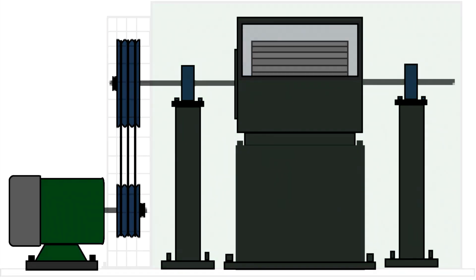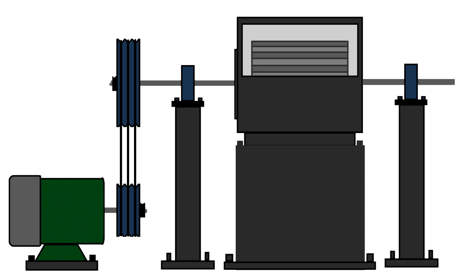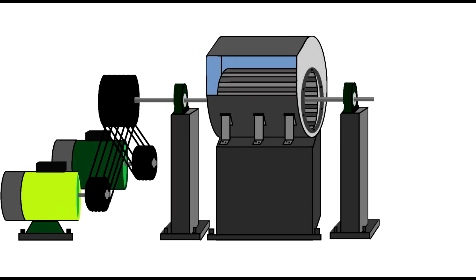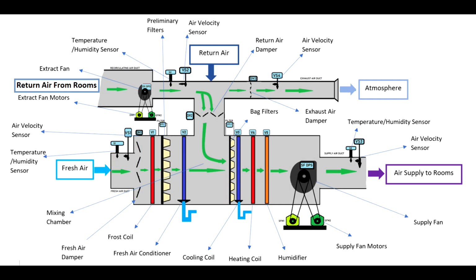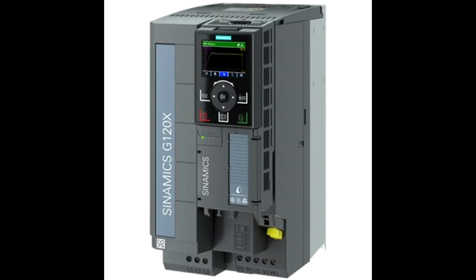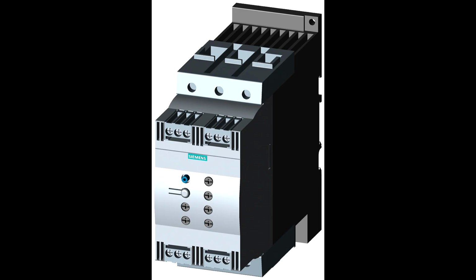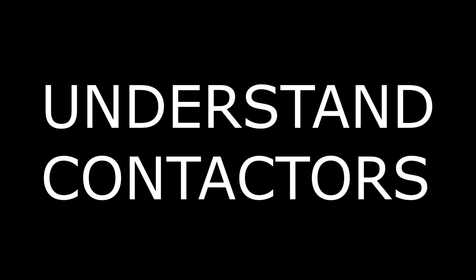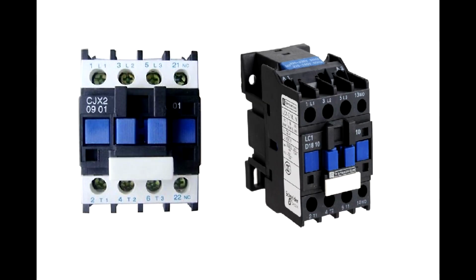Today I will talk only about contactors, and then I will make specific videos for soft starters and variable speed drivers. Let's take it slowly so you'll understand. Like I said before, amongst other parts, the air handling units have fan motors, and they have to be controlled either by variable speed drivers, like you see in this picture, or maybe soft starters if you don't have to vary the speed of the motor, or the contactors. And as I promised, today I'm going to keep it simple.